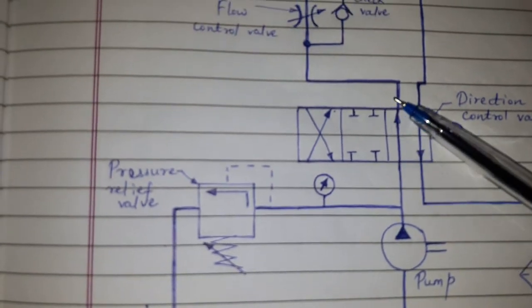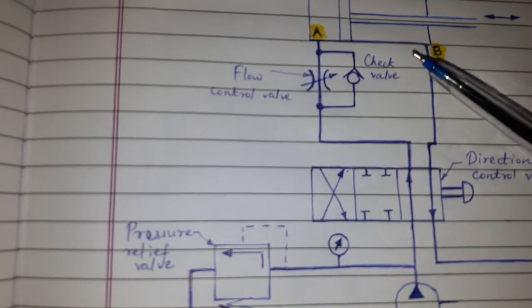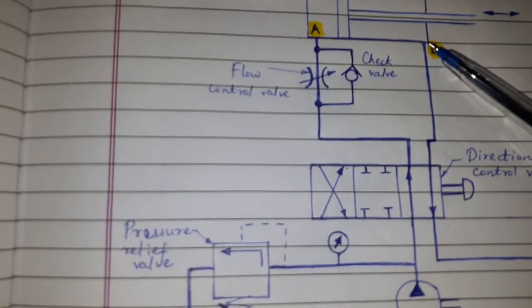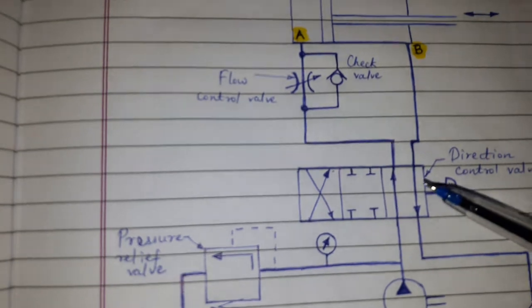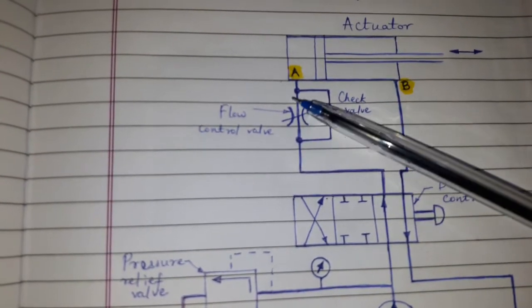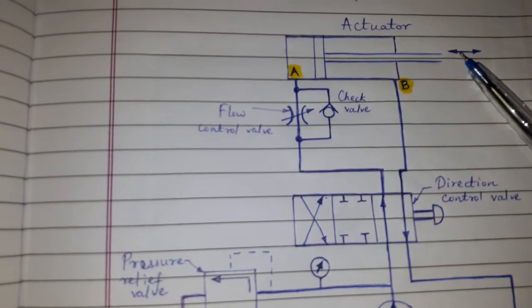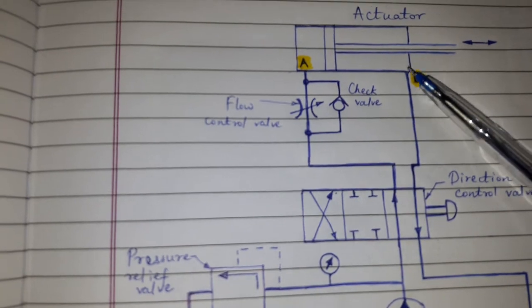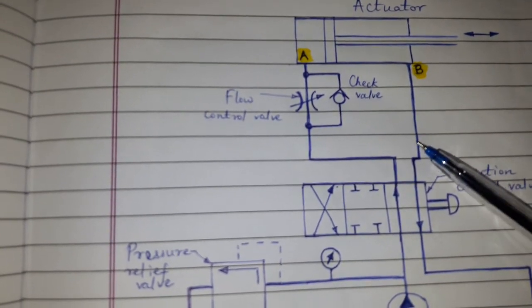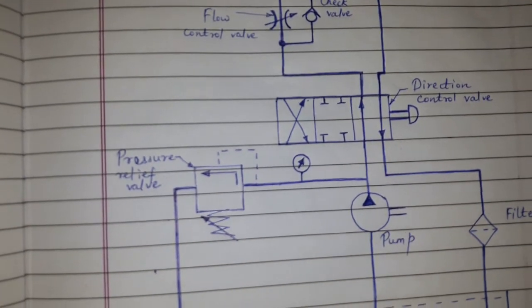The oil is directed to port A or B of the actuator by the directional control valve. When the oil enters through port A, piston will move from left to right. The oil from the other side of the piston will return through port B via directional control valve to the oil tank.